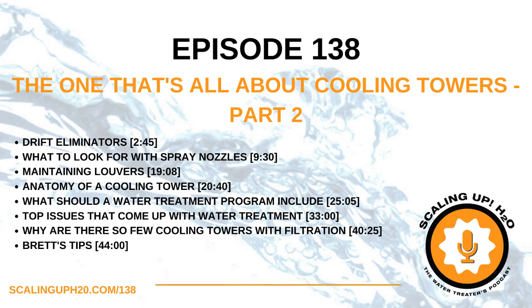So Brett, last week when we opened up the show, you said you had some tips with towers and evaporative condensers that could help the Scaling Up Nation. Do you mind sharing those with us? Yeah, so everybody's familiar with the open cooling tower setup, right? The large water volume, usually connected to a plate and frame heat exchanger or a chiller. So we mentioned last week the closed circuit coolers and the evaporative condensers with the coils. I just wanted to touch on a couple things to keep in mind when treating those units.